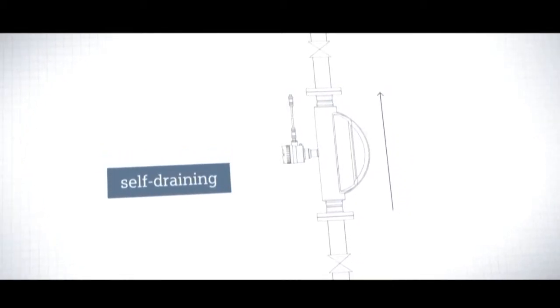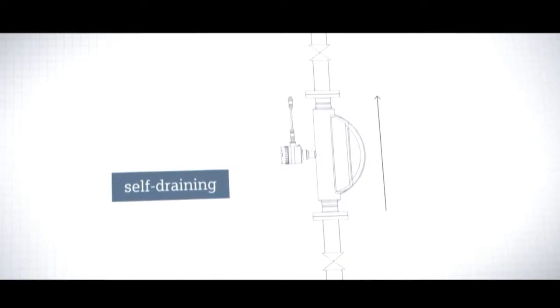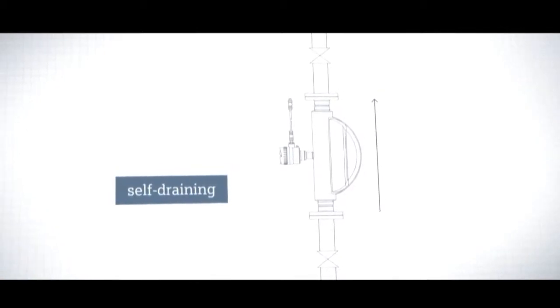Siemens recommends one of the following. For vertical installation with upwards flow, the pipe is constantly filled, avoiding bubble formation. This mounting position is also self-draining.